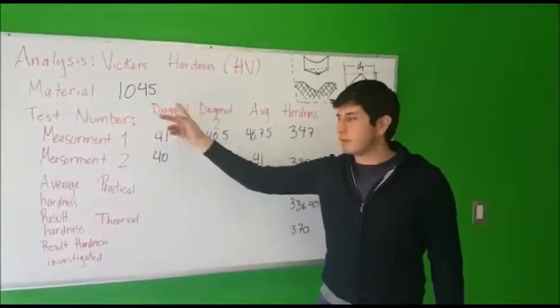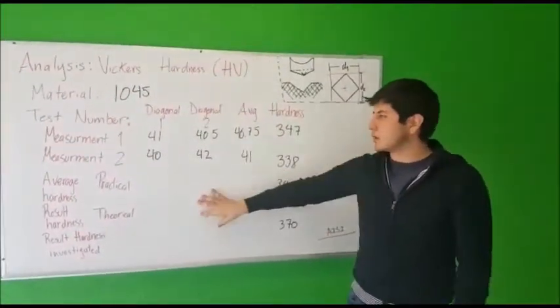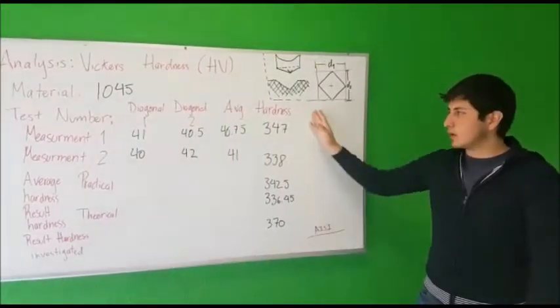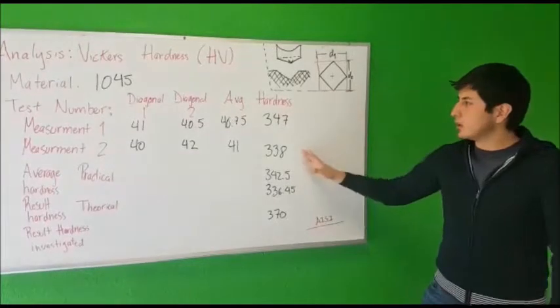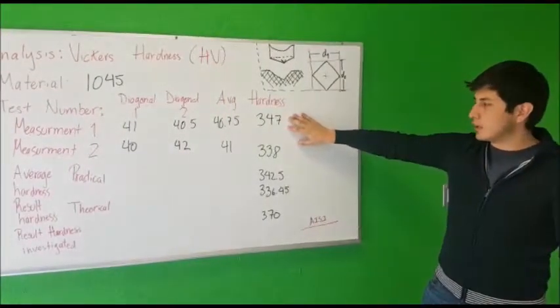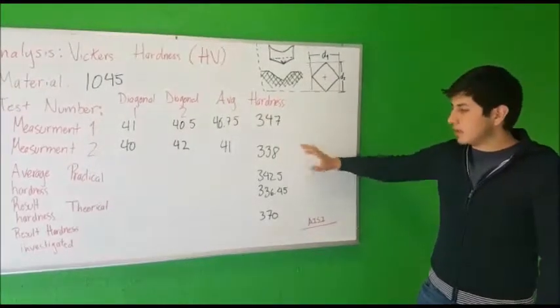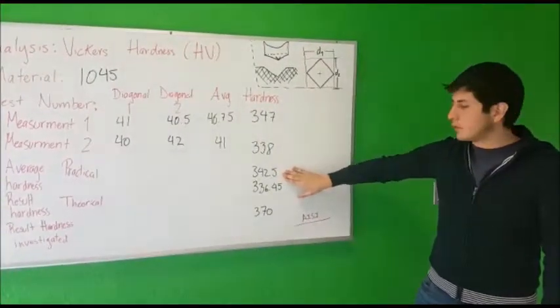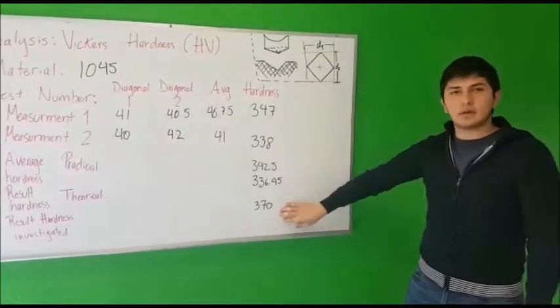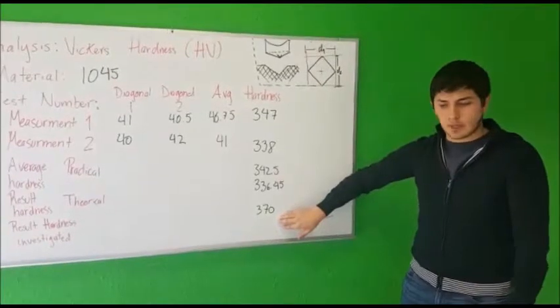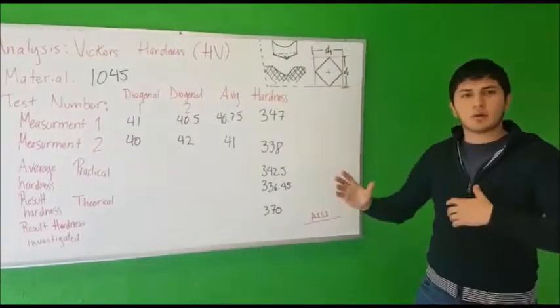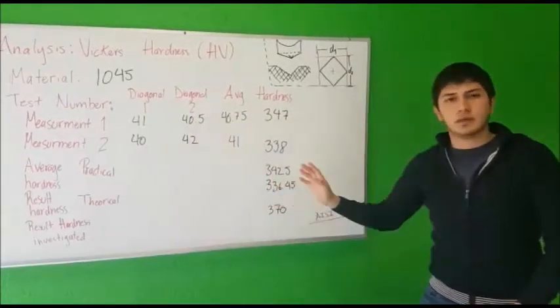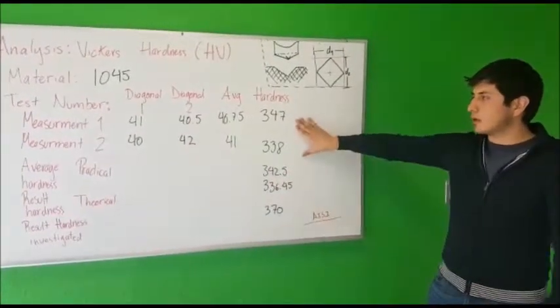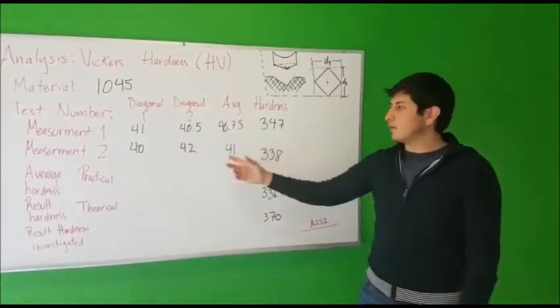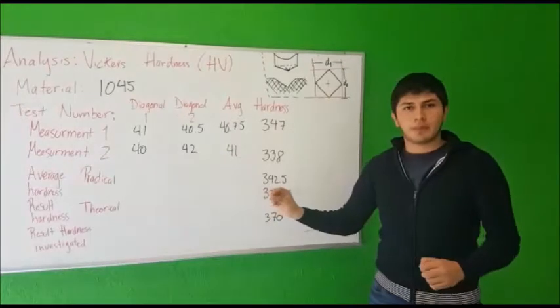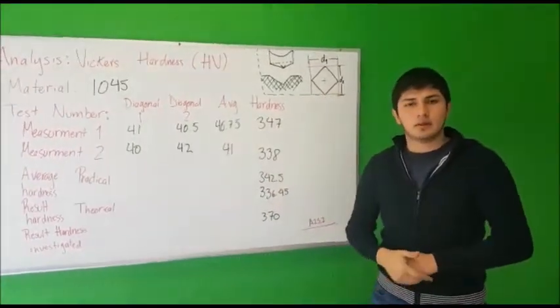Then for the steel 1045, we get this measure, where the unit of hardness is kilogram per square millimeter. Here we have 347, then 338. Then the average of those two is 342.5, and the real value is 370. If we compare the steel 1045 and the steel 1018, we can see that we get more hardness here because the diameters of the indentation are smaller than in the 1018 steel.